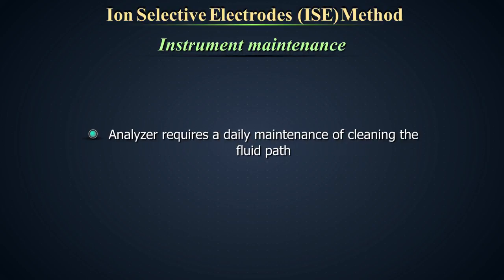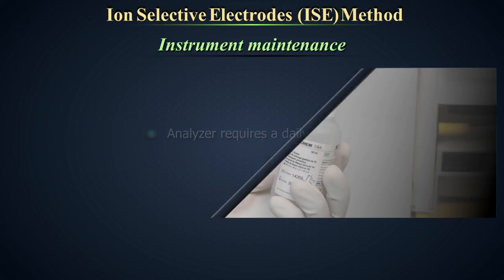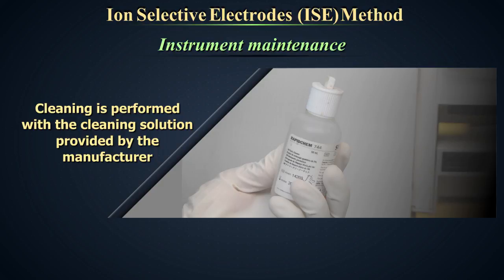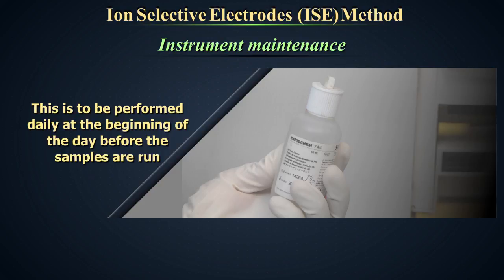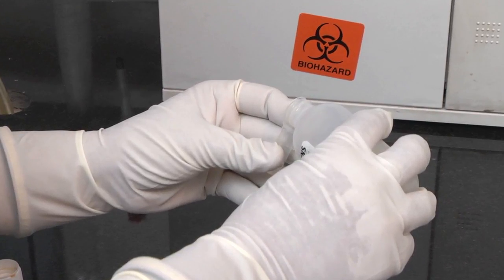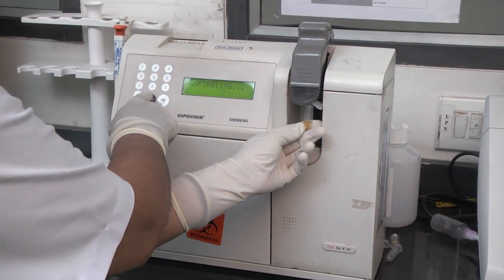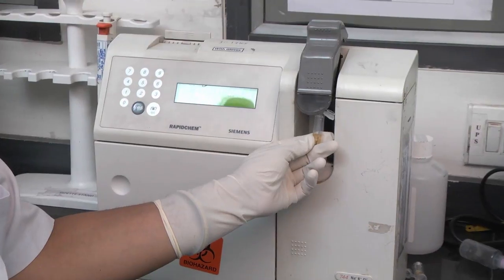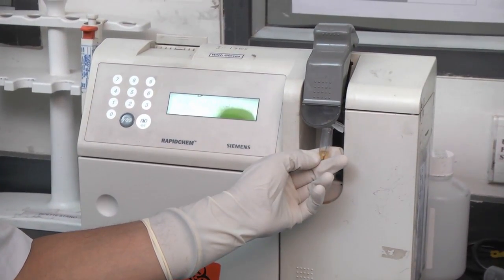Instrument maintenance. The analyzer requires a daily maintenance of cleaning the fluid path to remove protein deposits. Cleaning is performed with the cleaning solution provided by the manufacturer. This is to be performed daily at the beginning of the day before the samples are run. Take the cleaning solution in a clean container to avoid contamination of the remaining solution. Run the cleaning solution like a sample but in the daily cleaner mode. The cleaning cycle will be completed in 75 seconds.